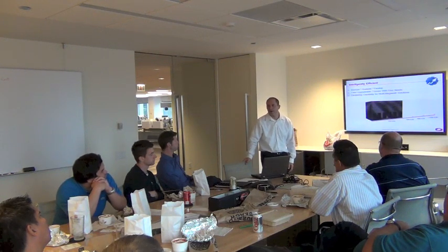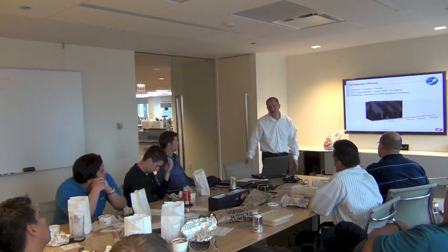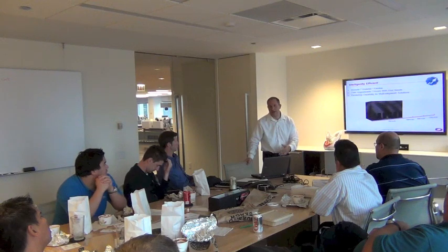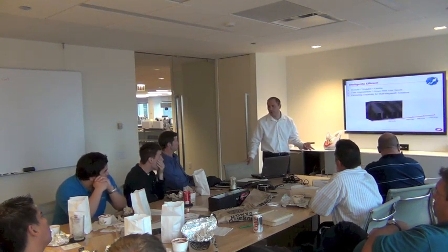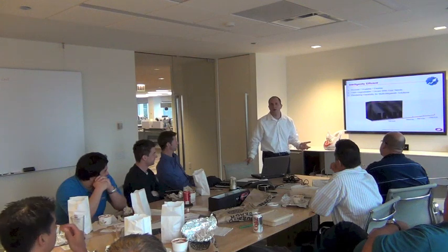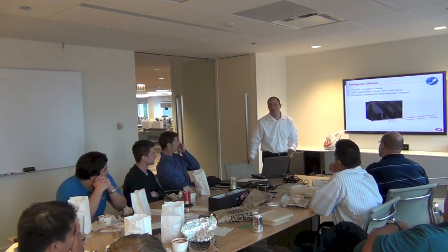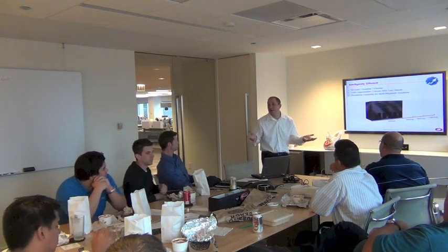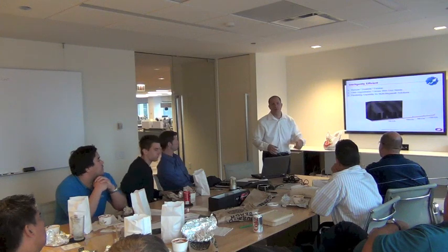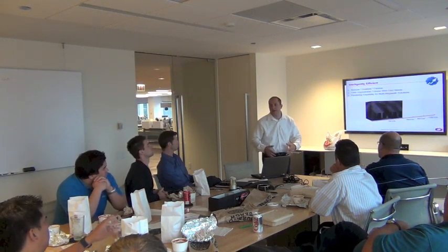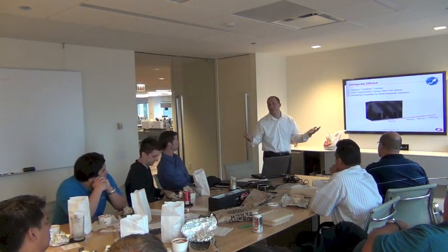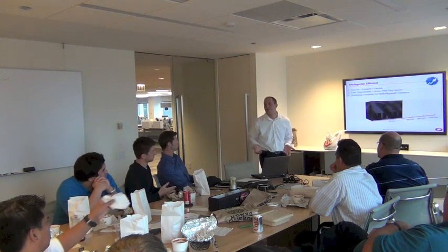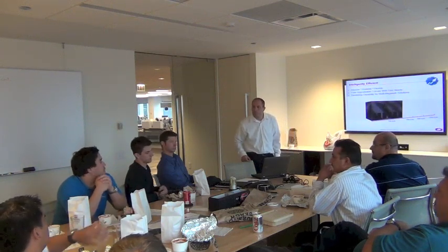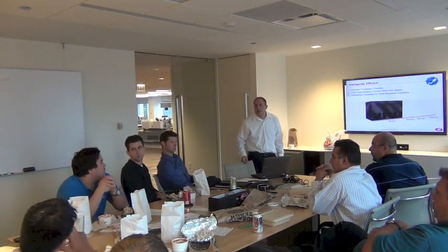A lot of times, on some of the further slides, we talk about heat, but we basically operate in a 32 to 140 degrees Fahrenheit environment. And a lot of times customers are like, oh, okay, well, I don't need air conditioning. Well, as engineers, you know that's not true. A UPS is putting off heat. If you don't have a way to remove that heat, or if you're not designing around that heat rejection, depending on the size of the room, it's possible that room will eventually heat up hotter than 140 degrees. So you don't necessarily need to cool.